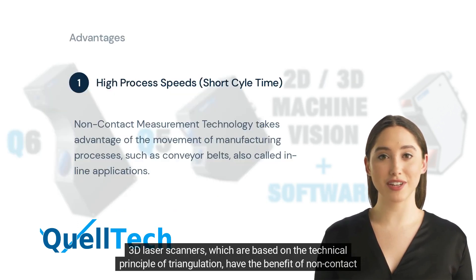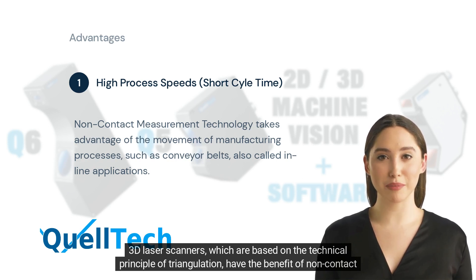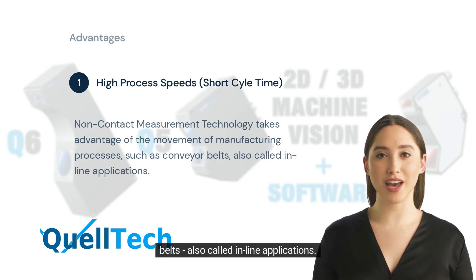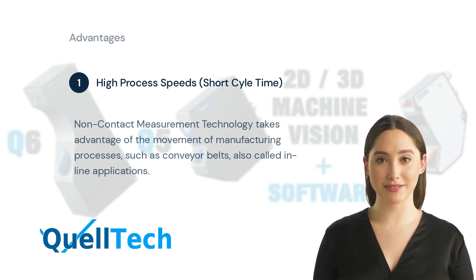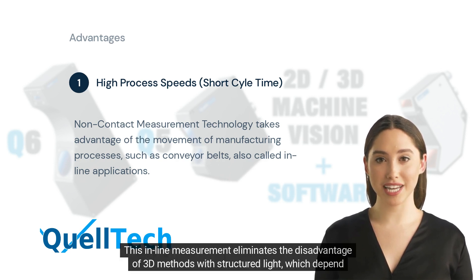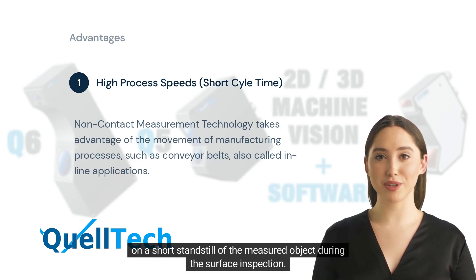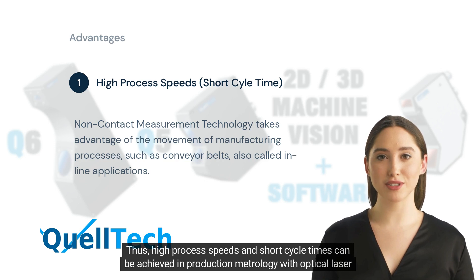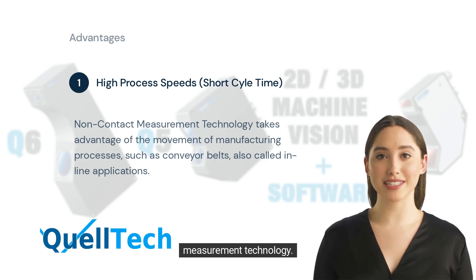3D laser scanners, which are based on the technical principle of triangulation, have the benefit of non-contact measurement technology that can take advantage of the movement of manufacturing processes, such as conveyor belts, also called in-line applications. This in-line measurement eliminates the disadvantage of 3D methods with structured light, which depend on a short standstill of the measured object during the surface inspection. Thus, high process speeds and short cycle times can be achieved in production metrology with optical laser measurement technology.